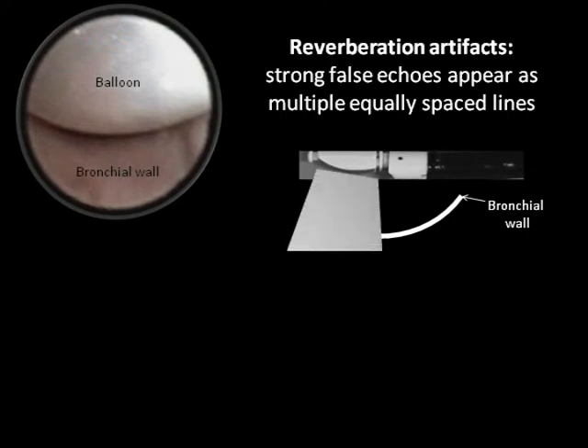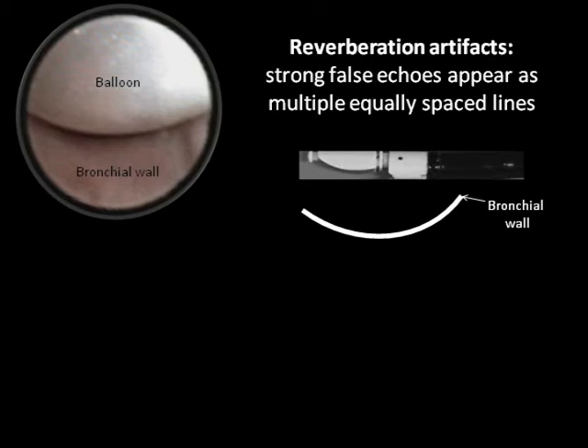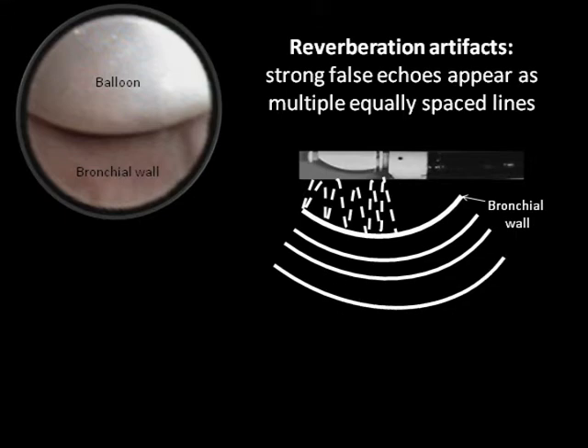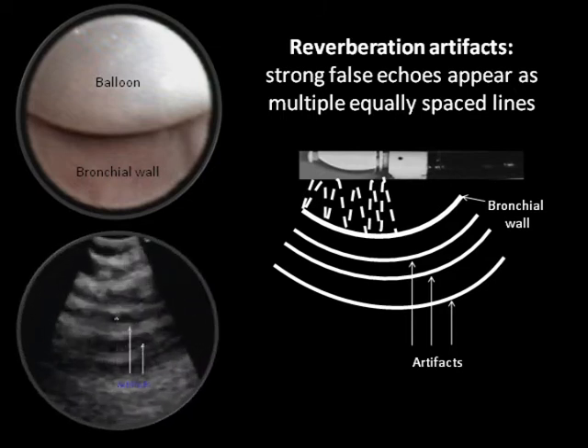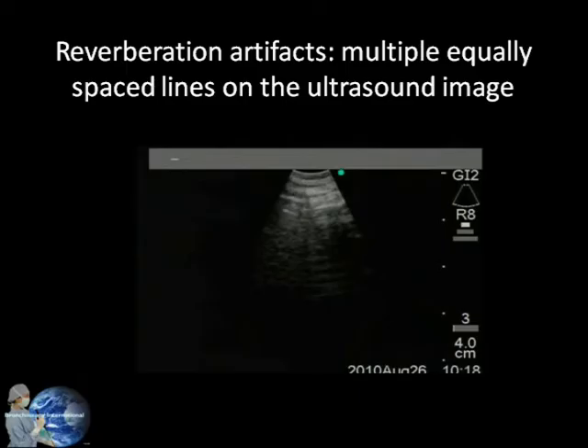Reverberation artifacts are strong false echoes that appear as multiple equally placed lines on the ultrasound image. These occur when the water-filled balloon of the EBUS bronchoscope is not in intimate contact with the airway wall. Subsequently, ultrasound waves are repeatedly reflected between the high-reflective airway wall and the transducer. Here is an example of reverberation artifact.